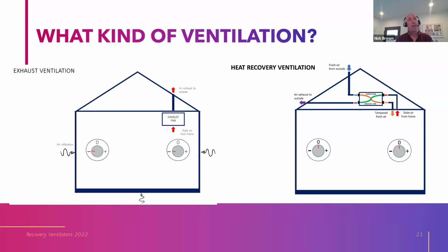So as a result of having roughly equal supply and exhaust airstreams, you have neutral pressure in the space, and you don't have the same air infiltration from uncontrolled sources. So in this manner, we're bringing in a more controlled set of outside air. And the energy code has a mandatory measure that says all supply ventilation systems and supply legs of balance ventilation systems must be filtered MERV 13. Okay, just like your return filter grill in a ducted HVAC system has to be filtered MERV 13, we want to get the outside air coming in the same way.